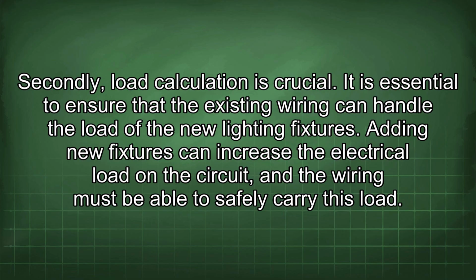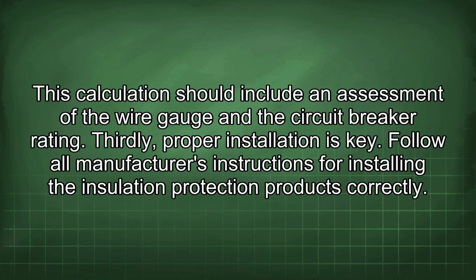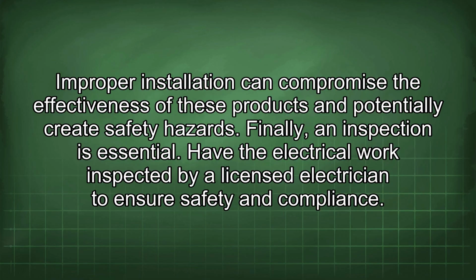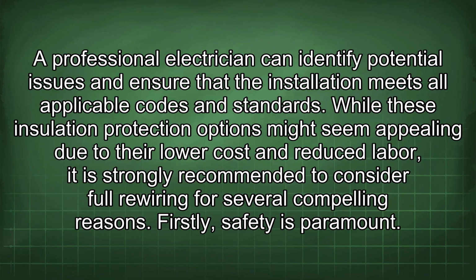Secondly, load calculation is crucial. It is essential to ensure that the existing wiring can handle the load of the new lighting fixtures. Adding new fixtures can increase the electrical load in the circuit, and the wiring must be able to safely carry this load. This calculation should include an assessment of the wire gauge and the circuit breaker rating. Thirdly, proper installation is key. Follow all manufacturers' instructions for installing the insulation protection products correctly. Improper installation can compromise the effectiveness of these products and potentially create safety hazards. Finally, an inspection is essential. Have the electrical work inspected by a licensed electrician to ensure safety and compliance. A professional electrician can identify potential issues and ensure that the installation meets all applicable codes and standards.